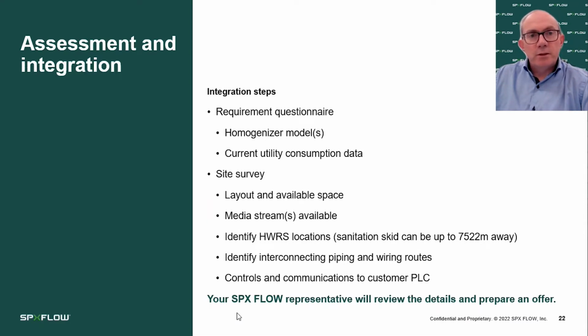Firstly, we ask you to complete a requirements questionnaire, which looks at the homogenizer model and current utilities consumption data. Very often we find that actual consumption is higher than the nominal consumption for a number of reasons, so water consumption may even be higher than you might think based on the homogenizer data.